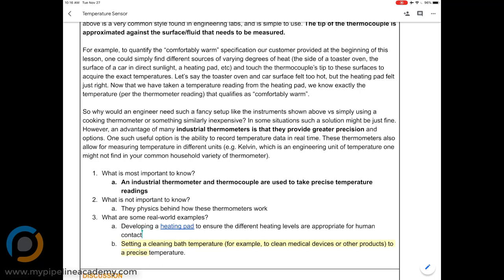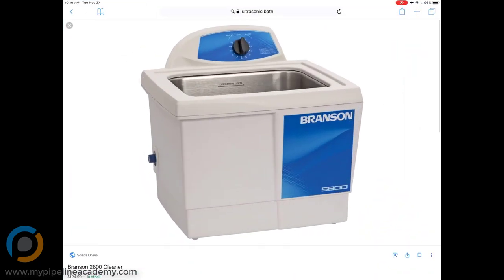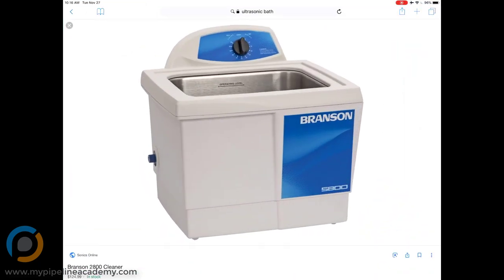Sometimes when cleaning a medical device you'll put it into an ultrasonic bath. So here's just a rough example, this is one ultrasonic bath. There are a lot of them out there that you can purchase. It's basically a stainless steel tub that you can see kind of in the center there, and then there are ultrasonic vibrations that this machine generates that propagate through the bath inside that stainless steel tub.